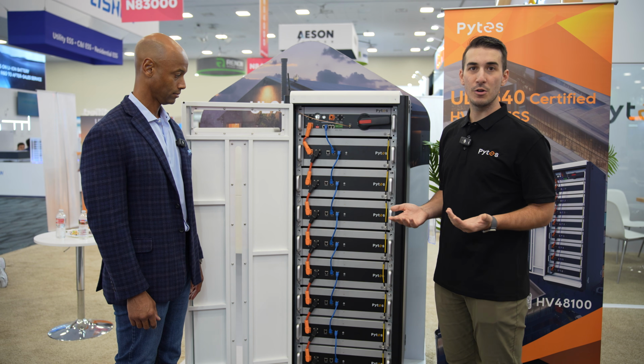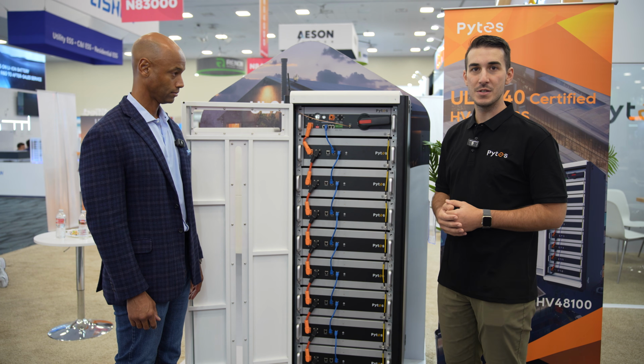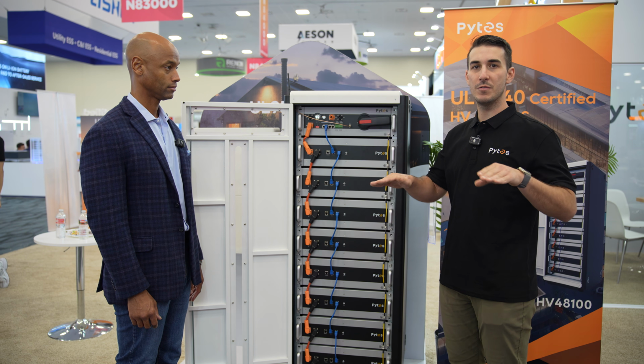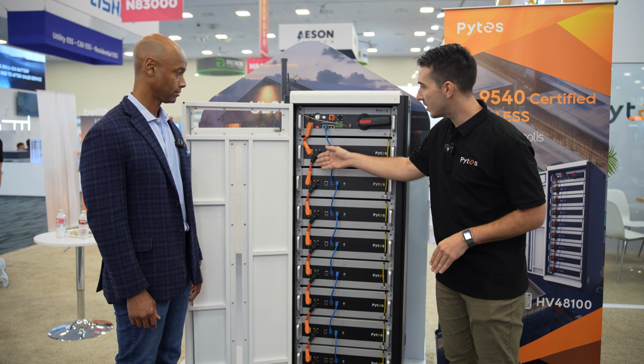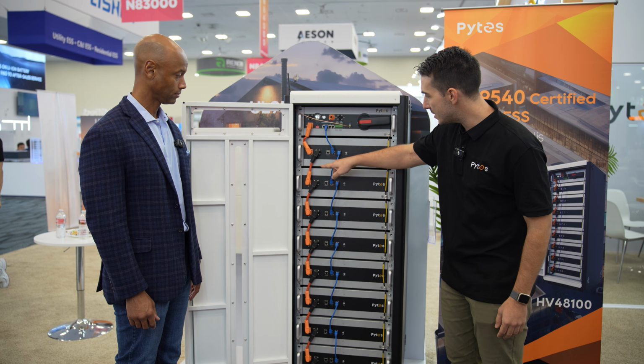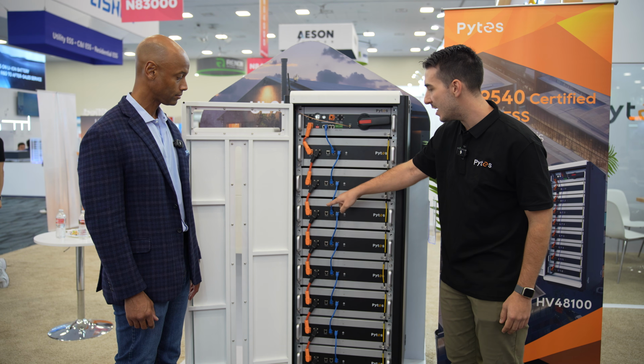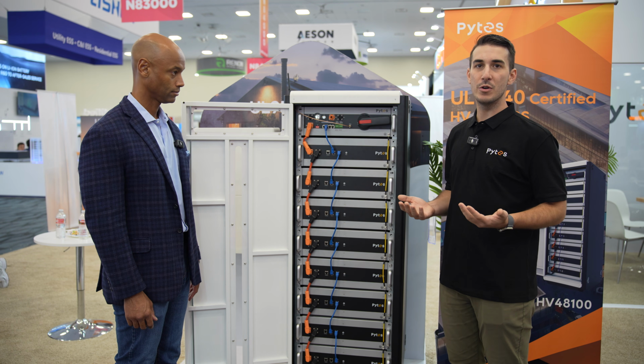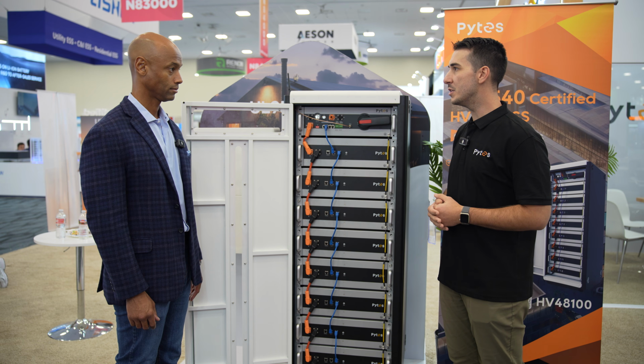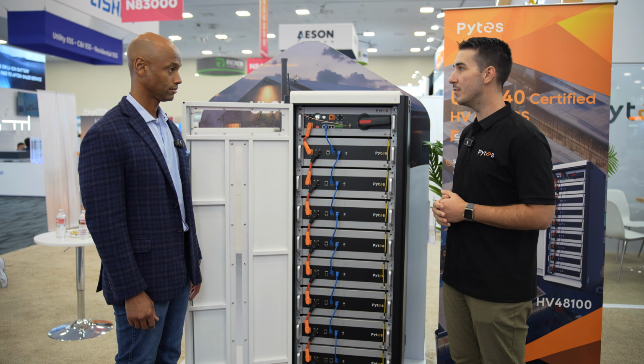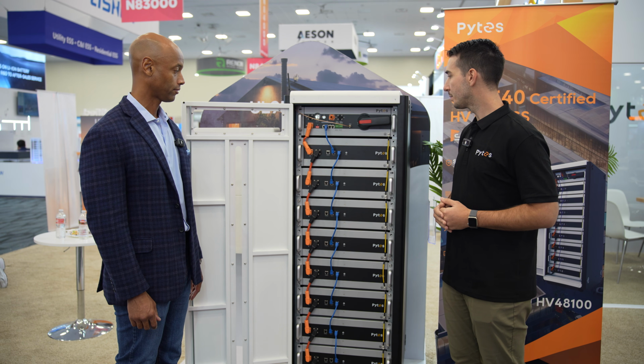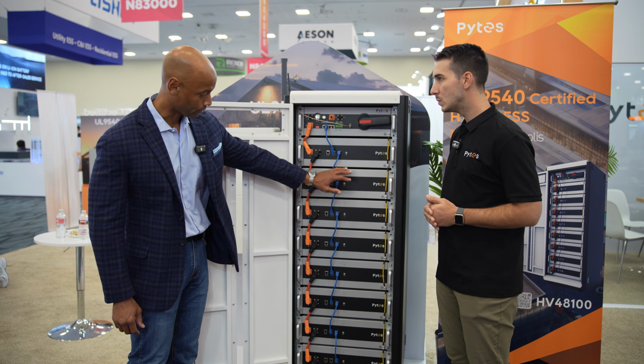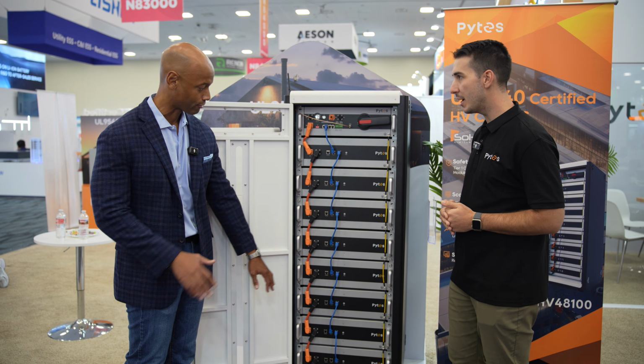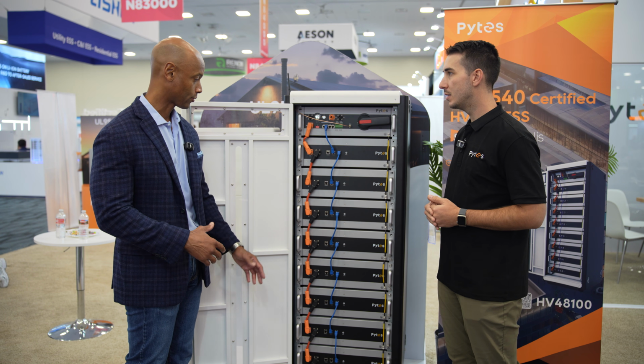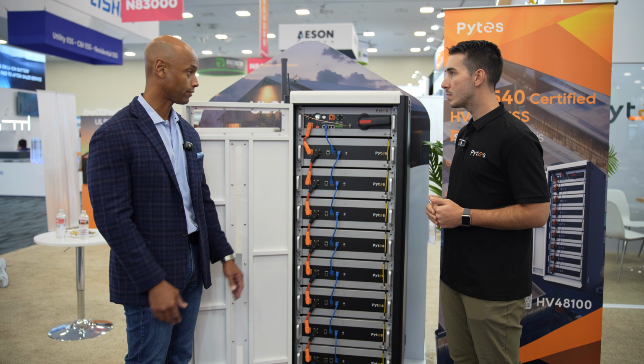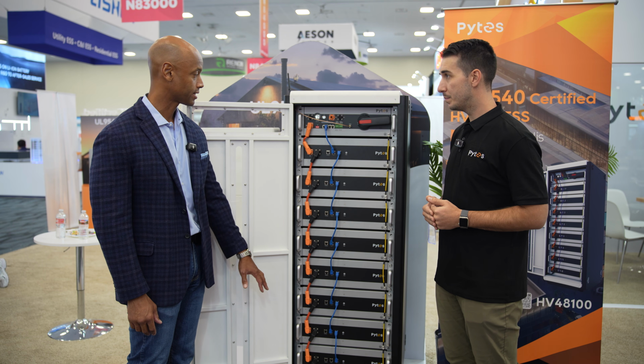The difference, as I said earlier, is instead of doing parallel connections, maintaining the whole system voltage at 48, we're now doing series connections. So we can see here moving down the stack, positive to negative, and that gets us upwards of 200 volts all the way up into the high 800 volt DC range. Right. So I'm just looking at the stack here now with what looks like 8 battery modules at roughly 50 volts apiece. Correct. So we're looking at just over 400 volts DC with this series connected stack.